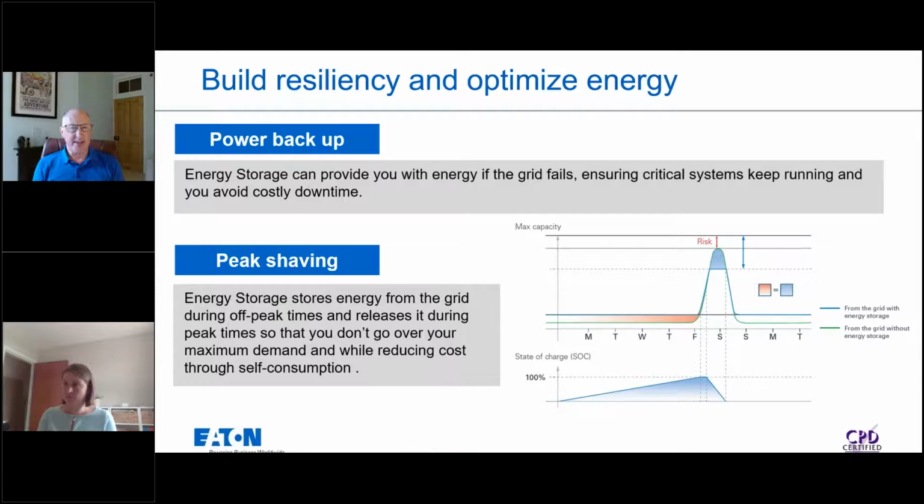Just to illustrate this with an example of a large retailer we recently worked with who were building a new store in Hampshire, they only had an available supply from the grid operator of 250 kVA. To get reinforcements to the supply to increase that, was needed reinforcements up to 132,000 volts, which apart from being astronomically expensive, was also not possible until at least 2030. So they got a 250 kVA available, and that was the limit.